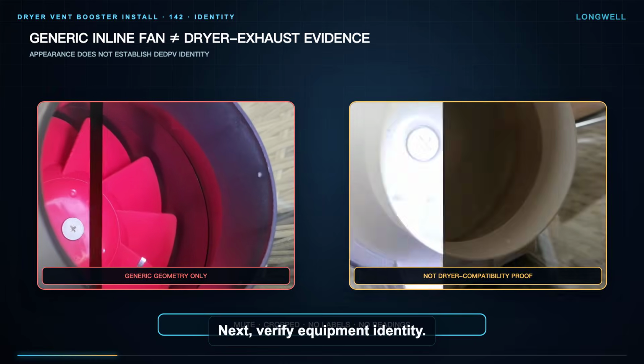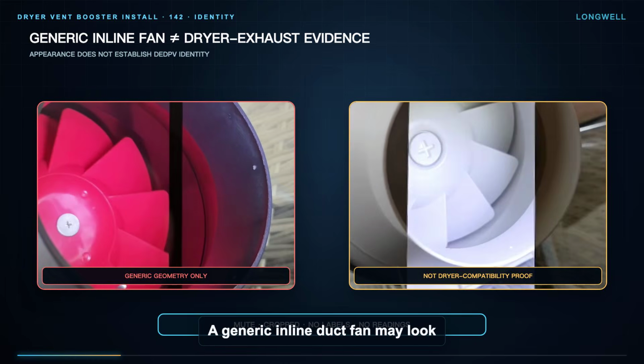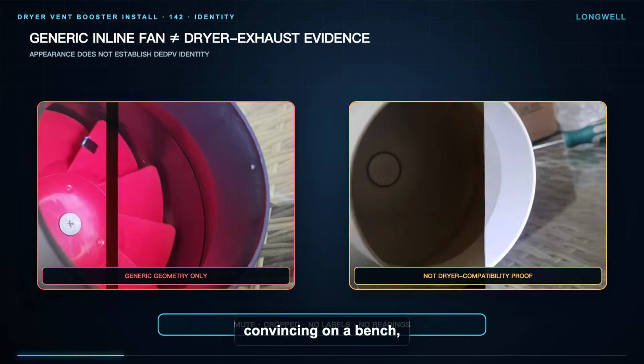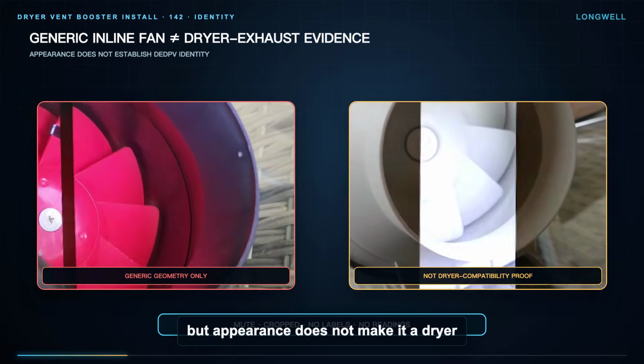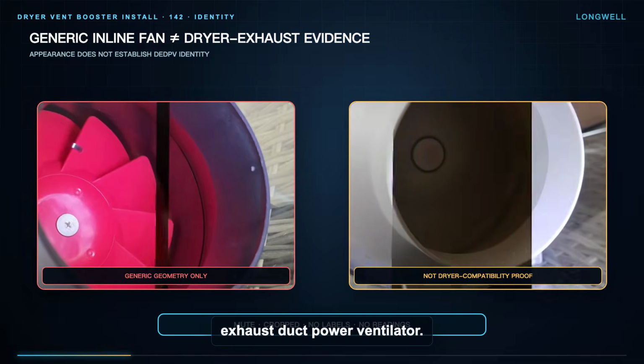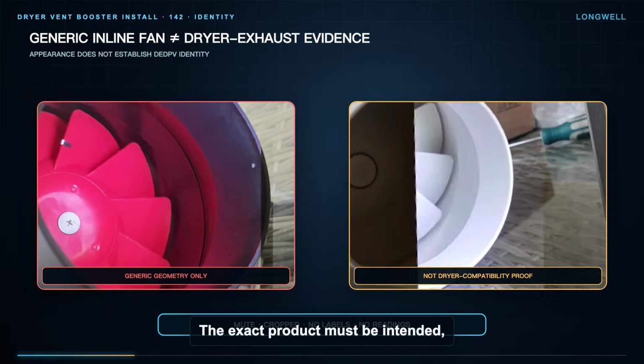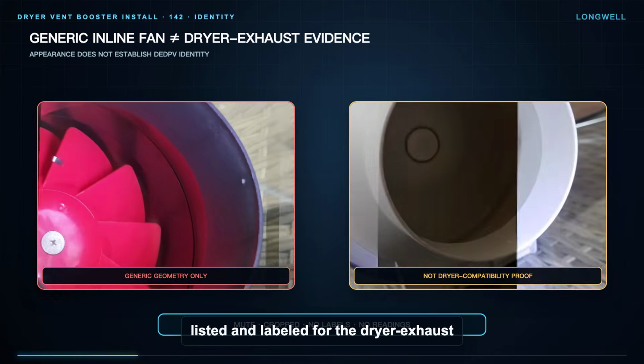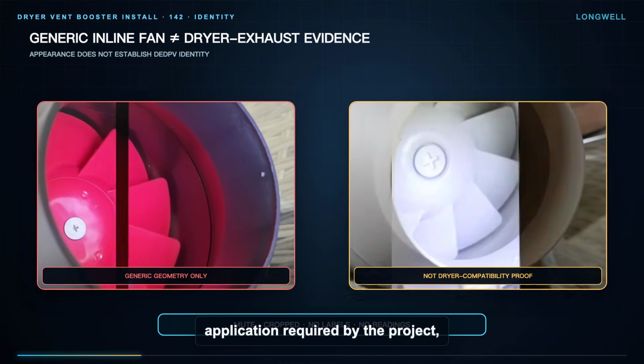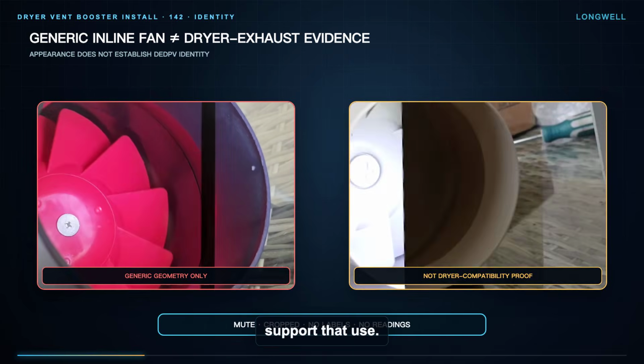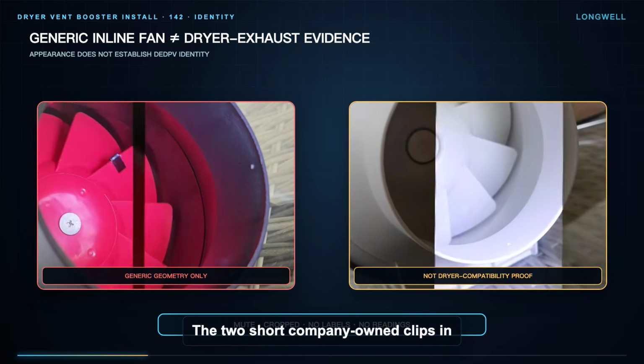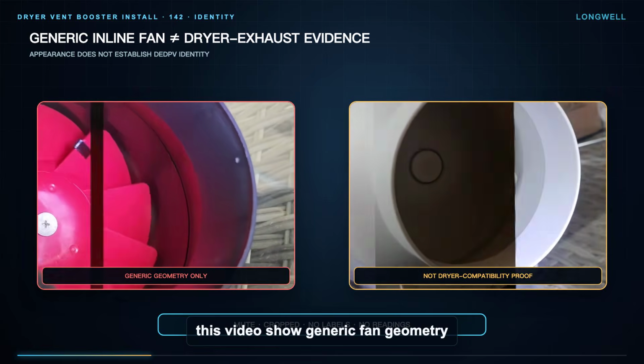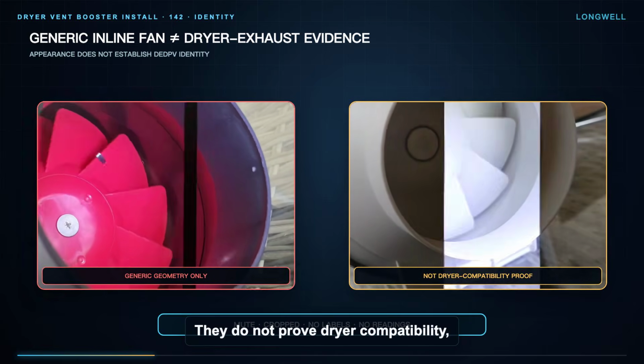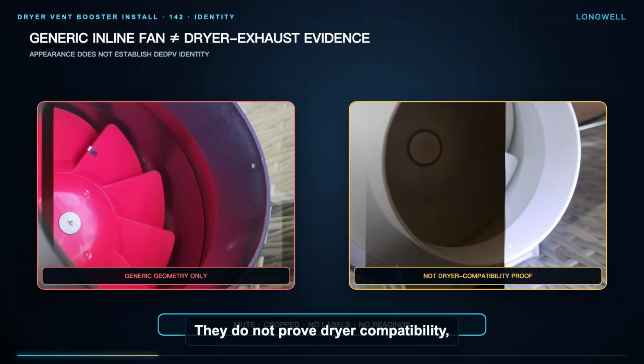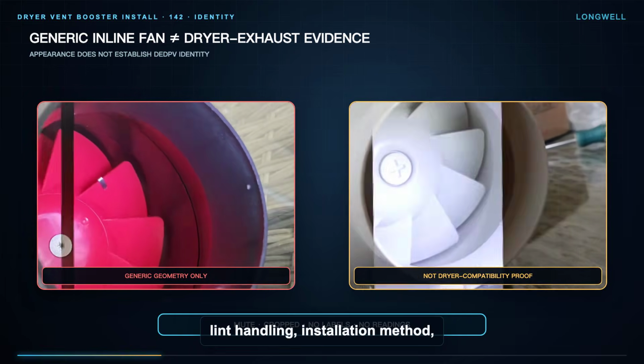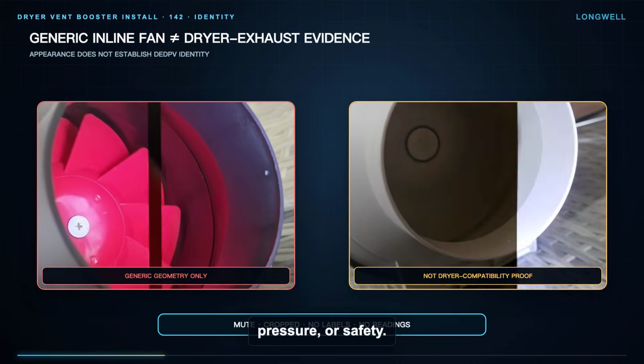Next, verify equipment identity. A generic inline duct fan may look convincing on a bench, but appearance does not make it a dryer exhaust duct power ventilator. The exact product must be intended, listed, and labeled for the dryer exhaust application required by the project, and its current documentation must support that use. The two short company-owned clips in this video show generic fan geometry only. They do not prove dryer compatibility, lint handling, installation method, certification, airflow, pressure, or safety.